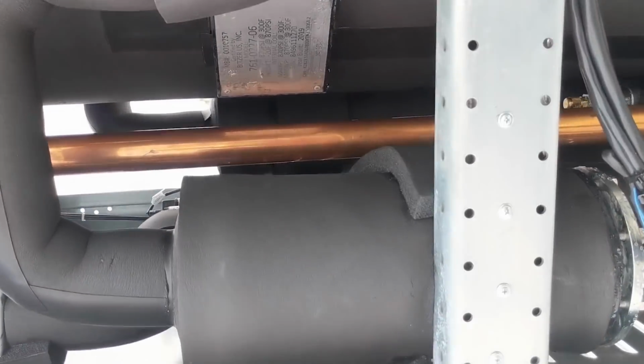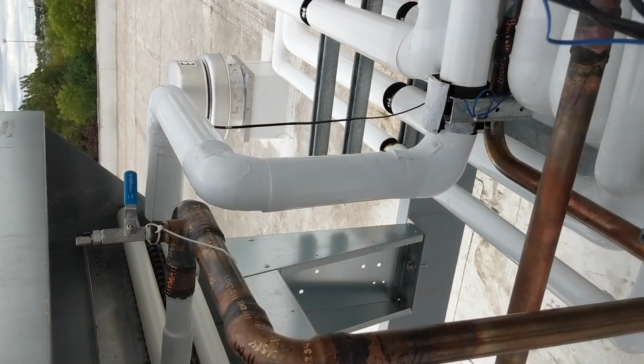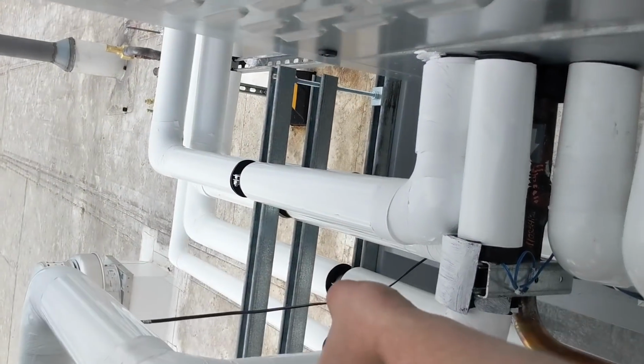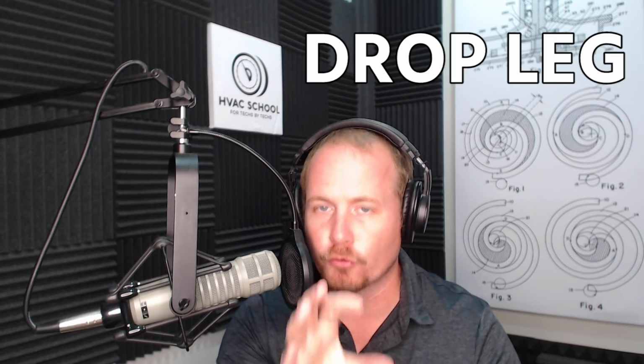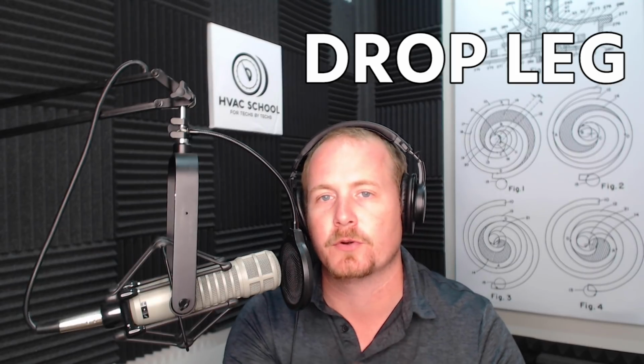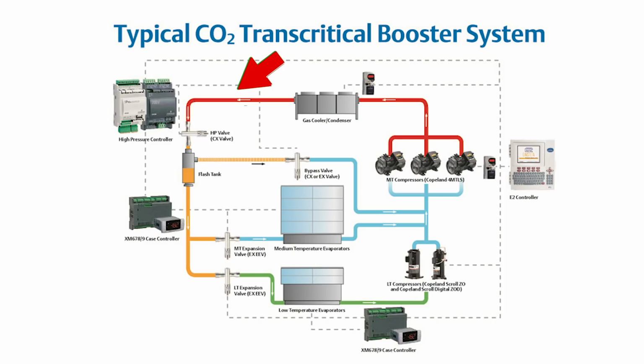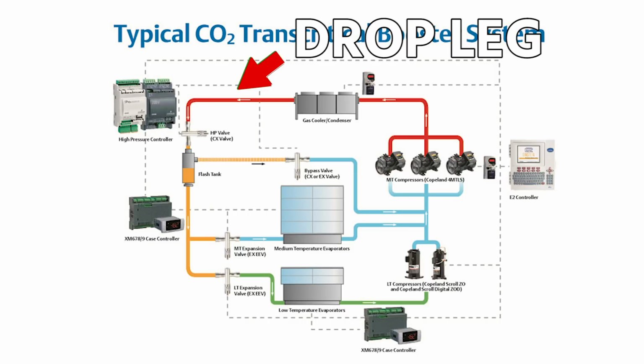So over here, we have our gas cooler. We got our drop leg coming out of the gas cooler, comes down, and comes back up to here. One word you're going to hear Kevin use here is drop leg. And drop leg in refrigeration is the line in between the condensers and the receiver. So generally the line that comes down from the condensers, that's what they call the drop leg.